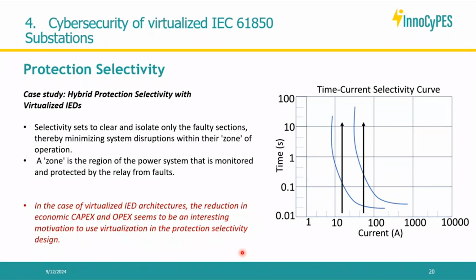So for us, we had two protections, but the virtual IED acts more like the curve to the left, meaning it acts on a smaller zone, faster. The physical IED acts on a larger zone with a higher threshold. Another motivation for this protection selectivity case study is that, as protection experts know, it's quite difficult to ensure complete selectivity because it's also expensive in terms of development or infrastructure.